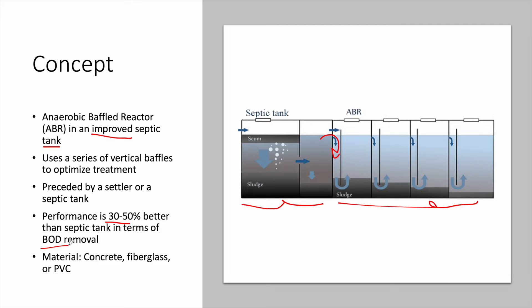An ABR system also achieves a high reduction of total suspended solids, making it ideal when using a wetland in secondary treatment, as it protects the wetland from clogging and failure. Materials that can be used include reinforced concrete, masonry, fiberglass, prefabricated systems, and even PVC. This system is highly modular, so additional baffles can be added if there is a higher flow or higher load entering the system.